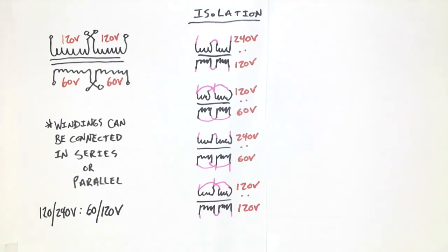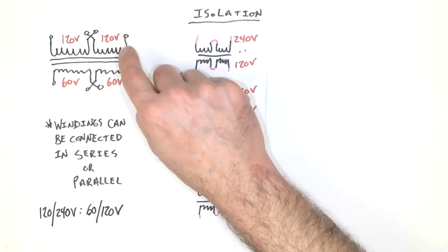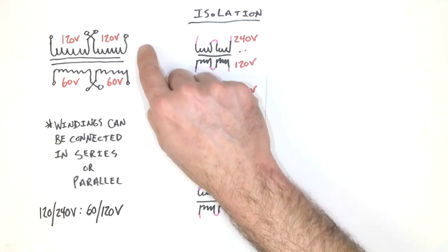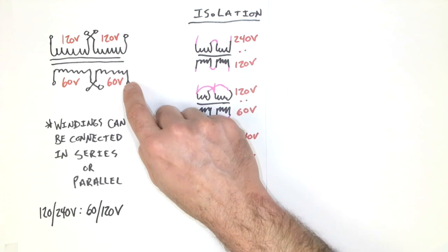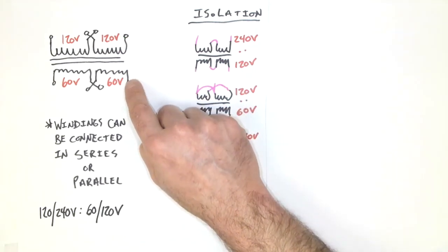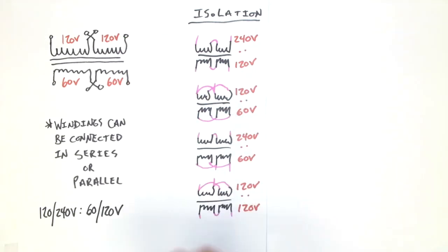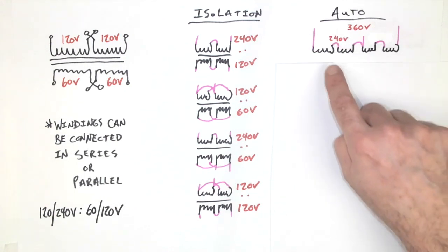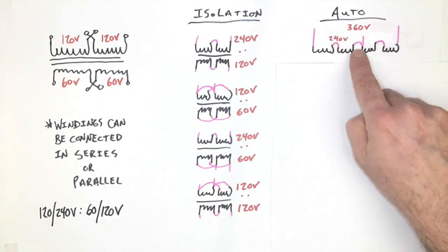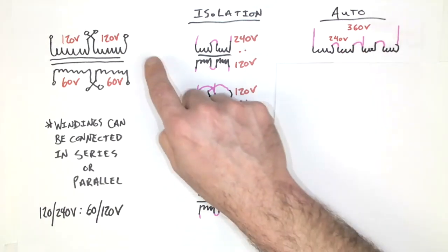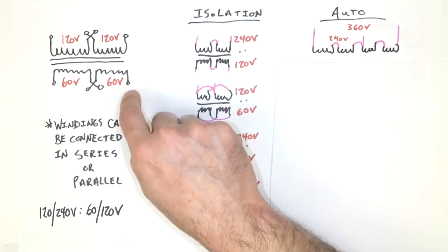And auto configuration means that we're going to have a series connection between the primary and the secondary. It's going to go from here to here, and that connection is going to remain consistent and the same for every single auto transformer connection we do with a buck boost transformer. So let's take a look at the different options that we have. We could put all of the windings in series, and that wire right there is what I was referring to that connects from here to here.